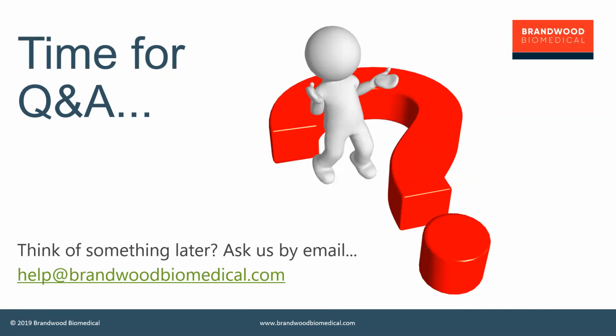Well, yes, the standard had changed and required a slightly larger study design, but your old tests produced all completely zero grade, so you were way down the bottom end of safe, and it was highly unlikely that adding another animal would have made a material change to the outcome. But apart from which, you've got 20 years of the product in the marketplace with the best testing of all, and that is use in actual patients.